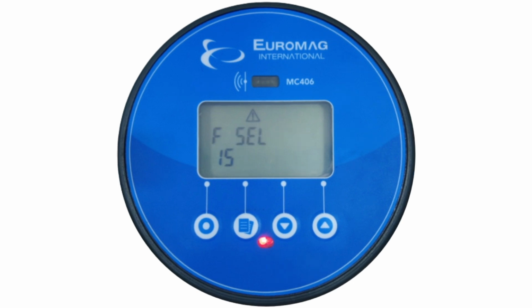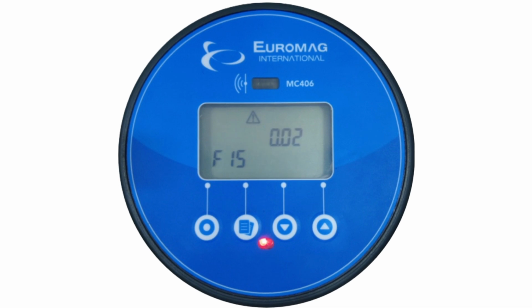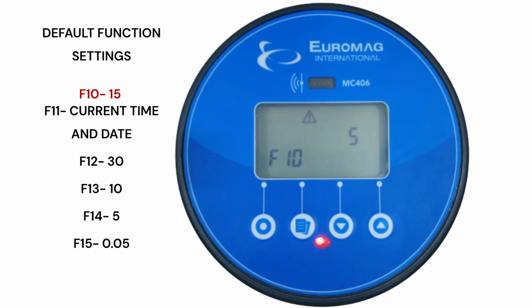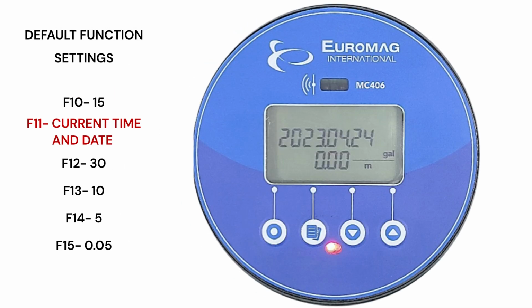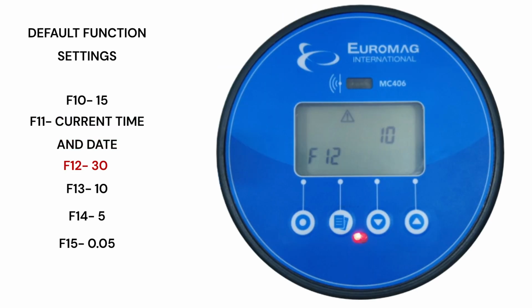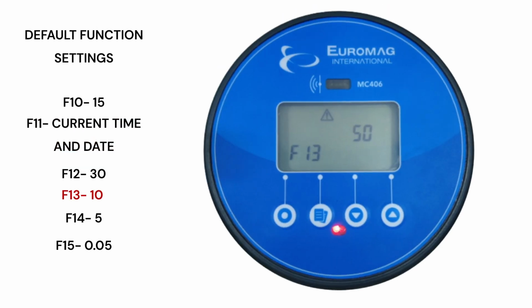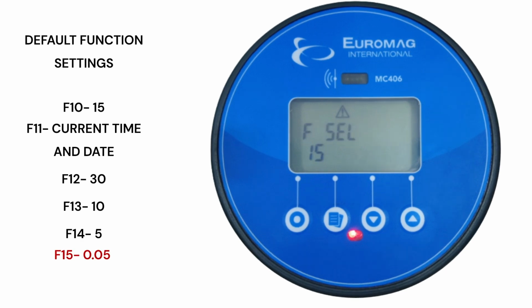Function number 15 is the low flow cutoff filter. This filter eliminates low values from the real-time display equation. With a value of 0.02, any samples with a velocity less than 0.02 meters per second will not be averaged. Congratulations on learning about Euromag electromagnetic flow meter filters for the 406 converter. Here is a list of the default factory settings if you need to revert back to the default settings.